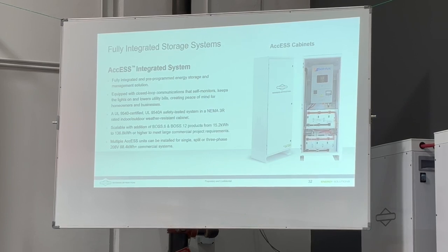This guy here constantly wants us to get the 15K in the cabinet. We've got installers that want the 15K in the AccESS cabinet because it's a really nice plug-and-play solution. But it's difficult from an engineering perspective without designing a cabinet specifically for the 15K. And the 15K is already outdoor rated, so just install the inverter on the wall. I know it's not plug-and-play that way, but it's nice to have one.